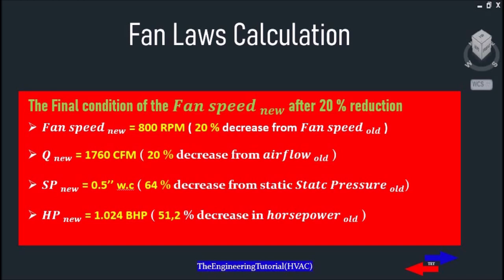So the final condition of the new fan: we have reduced the airflow by 20 percent, from 2200 CFM to 1760 CFM. That change has caused a reduction of 64 percent in static pressure, calculated according to the square of the speed ratio. It has also caused a reduction of 51.2 percent in horsepower, calculated according to the cube of the speed ratio, which is directly related to how much energy is required to run the fan. So a 20 percent reduction saves us 51.2 percent of energy on the electrical bill.